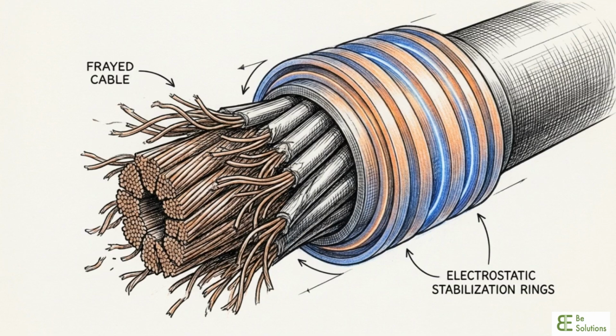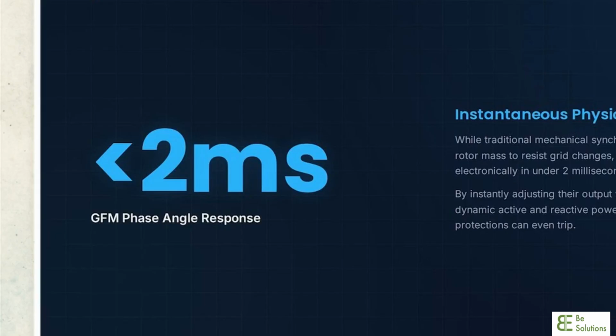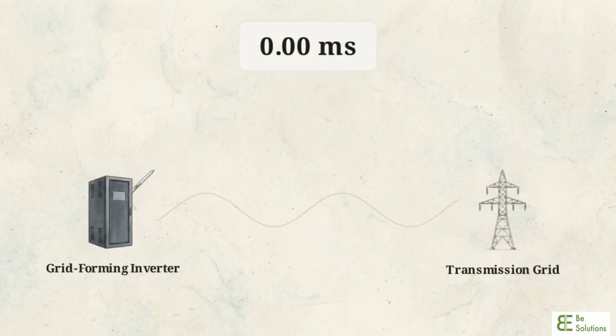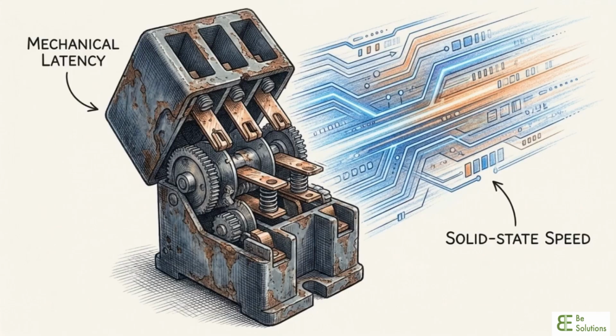This image highlights the speed of this digital emulation, which outpaces the mechanical hardware it replaces. Look at this data point for phase angle response. By immediately calculating the deviation, a grid-forming inverter adjusts its output voltage phase angle and injects dynamic active and reactive power in under 2 milliseconds. This stabilizes the grid before mechanical protection relays even register that a fault has occurred.